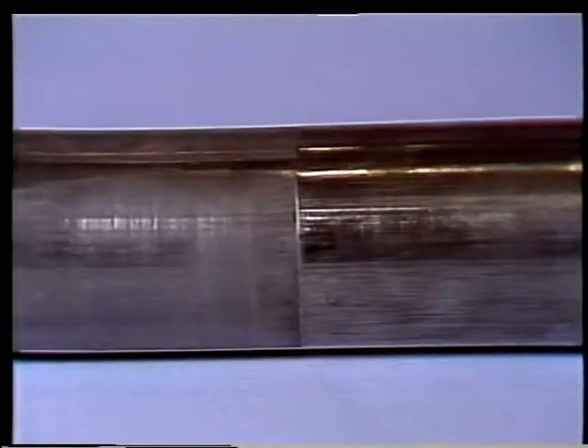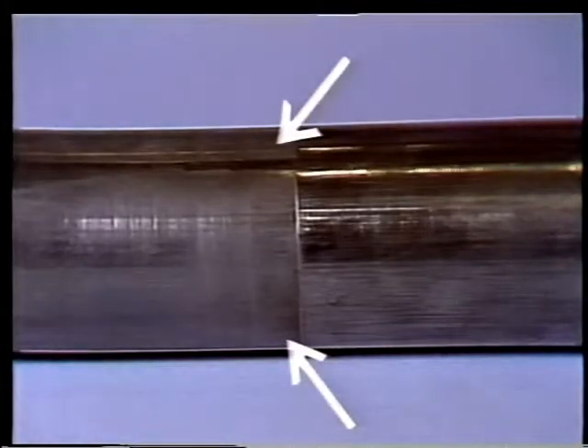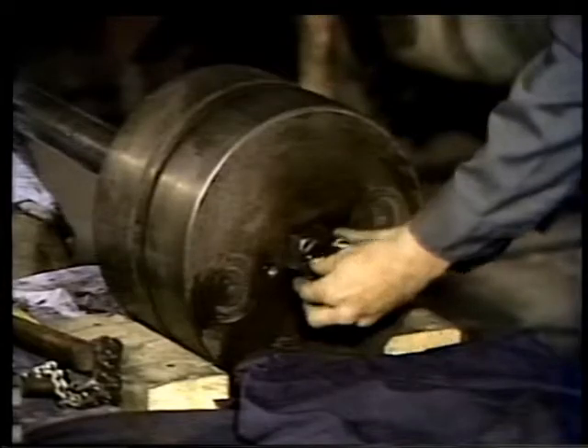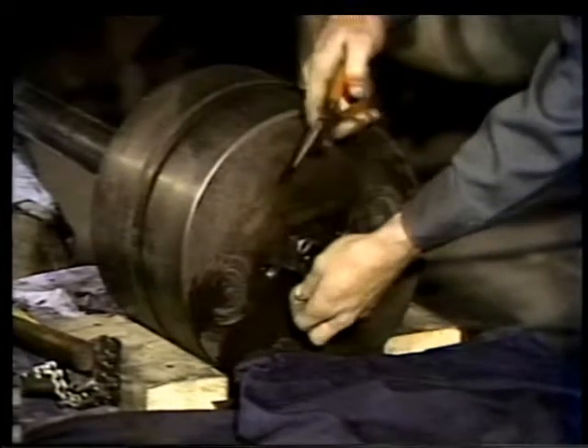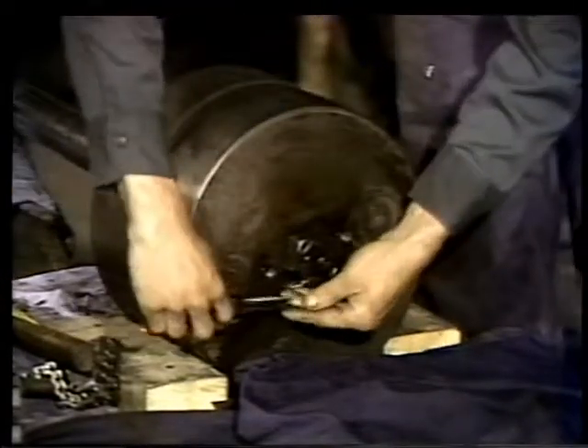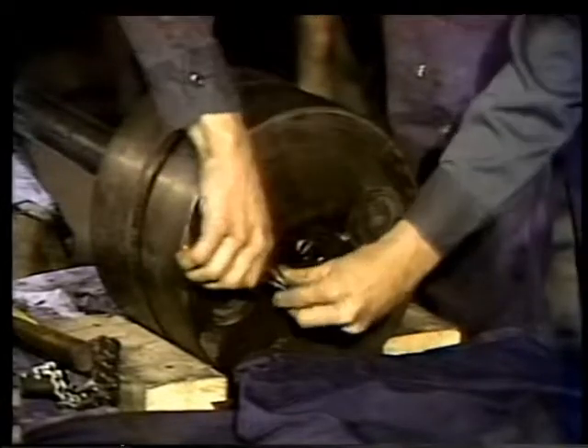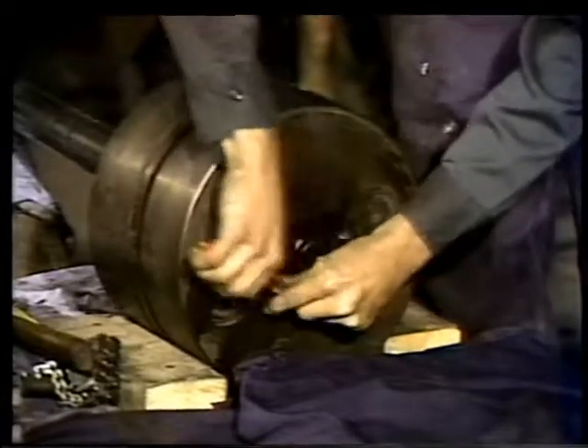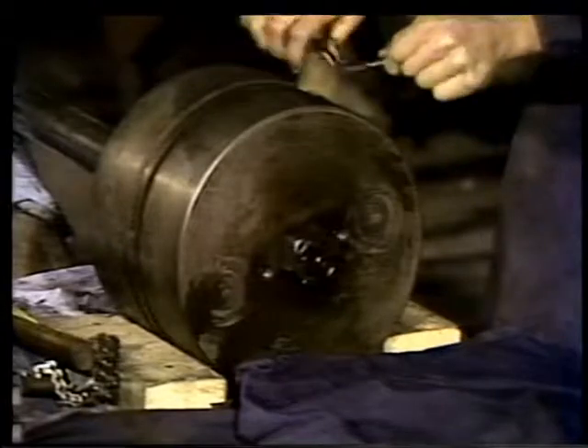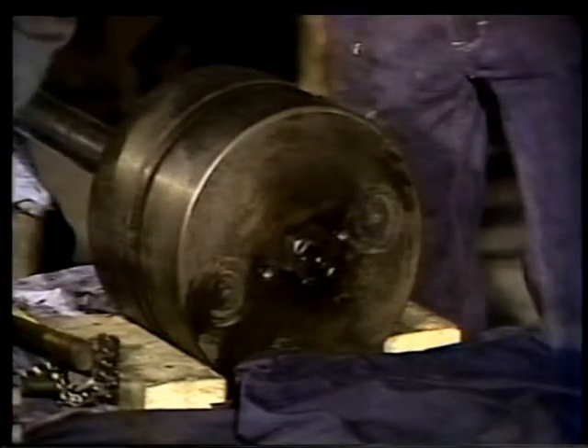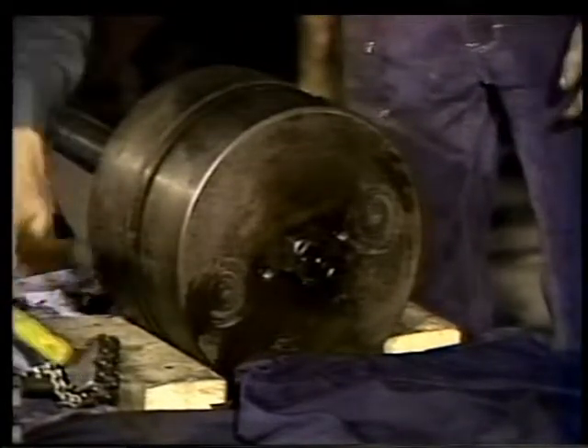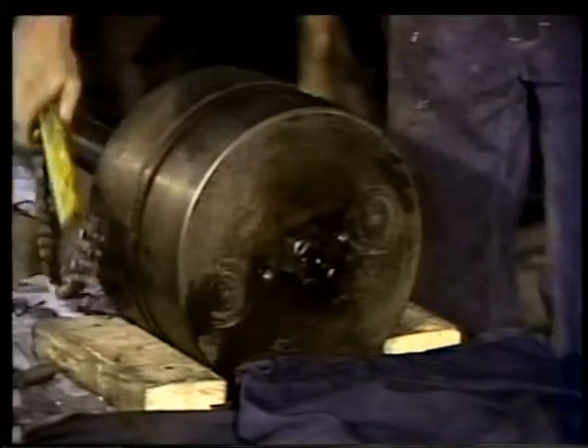The piston rod is inspected too. The oil wipers have worn this one down. To take out the piston rod, you have to remove the cotter pin from the piston rod nut. Then you remove the piston rod nut itself. To do this, you need to keep the piston rod from turning.